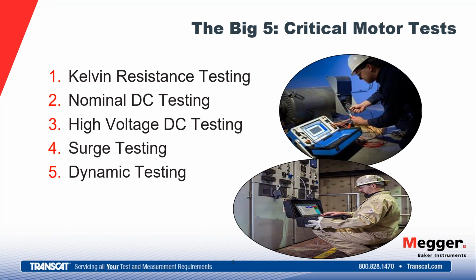The third test is also a DC test, but here we're going to bring that voltage up higher than nameplate to thoroughly evaluate that ground wall insulation, giving us a little more information than our low voltage test gave us. So again, we're going to be evaluating that motor to voltages it sees similar during opening and closing operations of the breaker. So we're going to simulate that and see how the ground wall insulation behaves, how it responds to that. The fourth test to take a look at is surge testing.